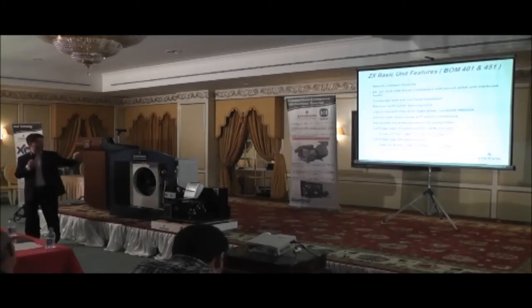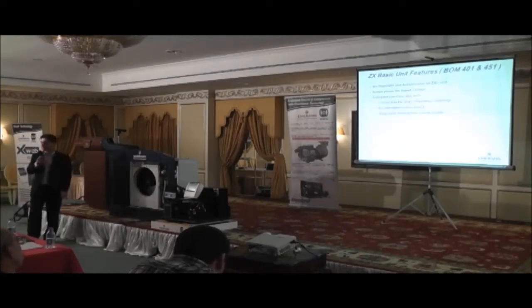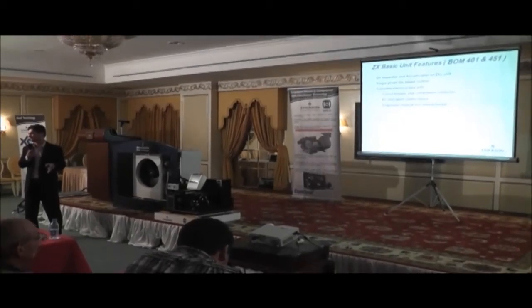Now these switches are preset, you cannot change them. So for example, on the HP, it will cut out at 30 bar and reset at 24. So these are presets. As I mentioned before, on the ZXL unit, you've got a receiver and accumulator fitted already. You have the fan speed control, and then you've got the complete electrical box. What do we mean by a complete electrical box? We have the switchgear to operate the compressor, and we have the electronic boards which are going to protect that compressor.